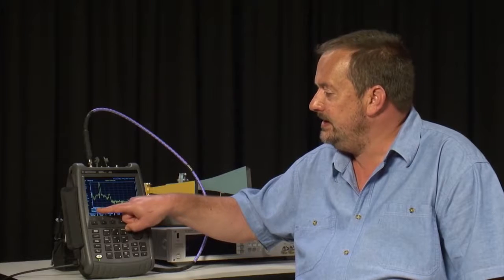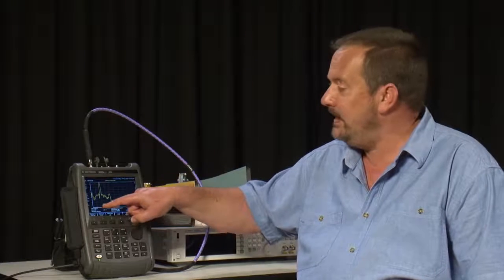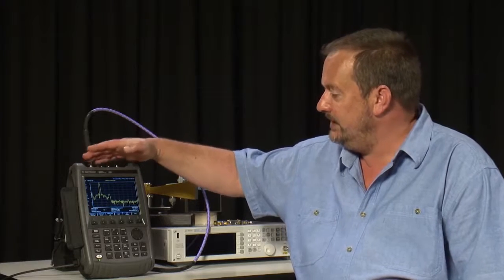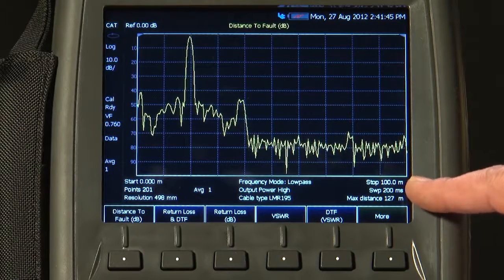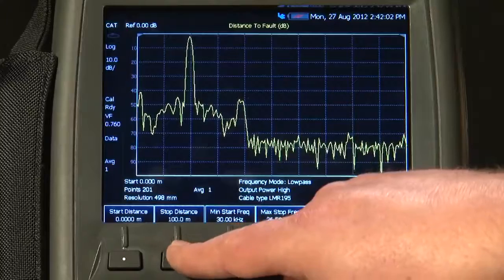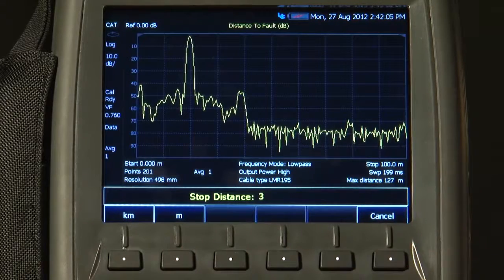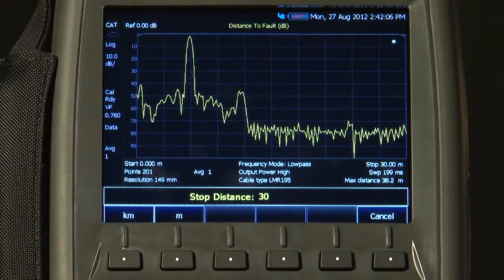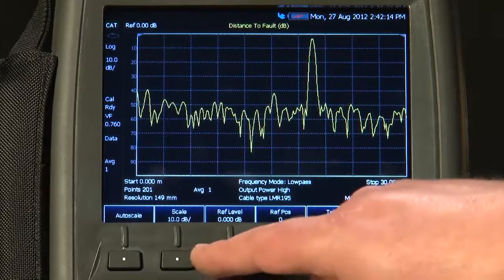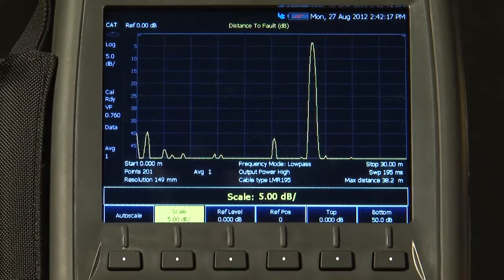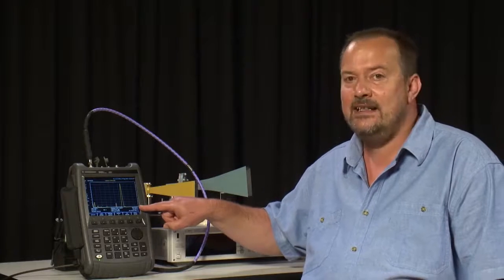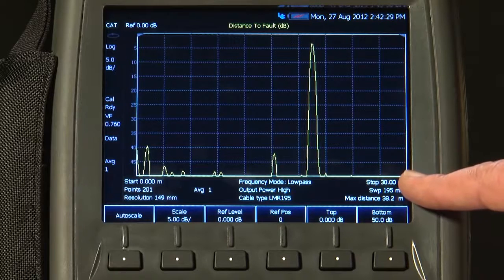The Start Distance is 0 meters. That is the calibration plane, which here, I am just using the CalReady again, is at this point here on port 1 of the FieldFox, and the Stop Distance is 100 meters. Now, I know this cable run is less than 30 meters, so if I press the Frequency Distance button and select Stop Distance, I will type in 30 meters. And the other thing I will do is change the Scale per Division to 5 dB per Division. Now, on the display, we are sweeping from 0 meters to 30 meters, and we can clearly see the reflections at the various points along the cable.